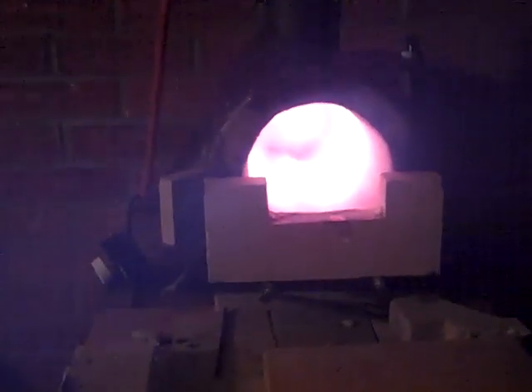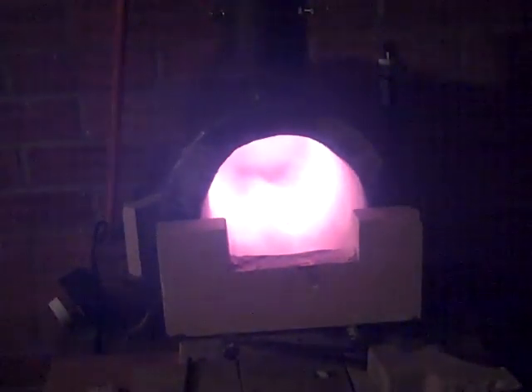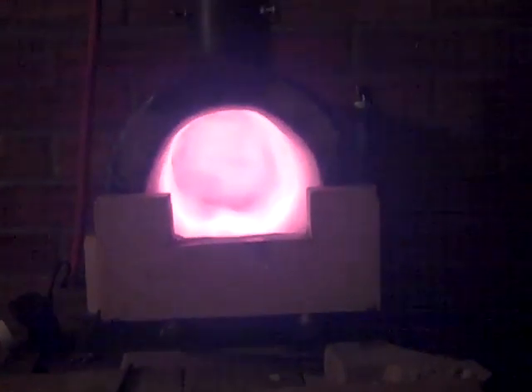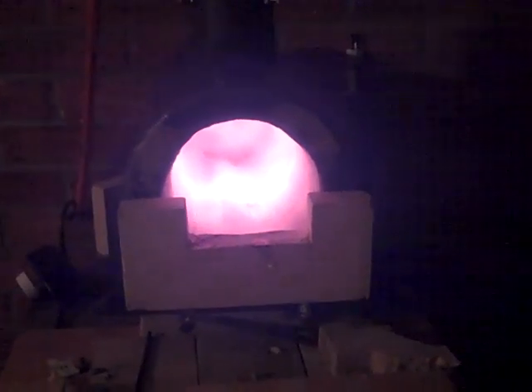Okay, this is cool. I've had the burner off for — you can see the blower's not even on it. It's been off for at least thirty seconds now. It is still smoking hot in there. The Satanite is doing a good job keeping that heat in.